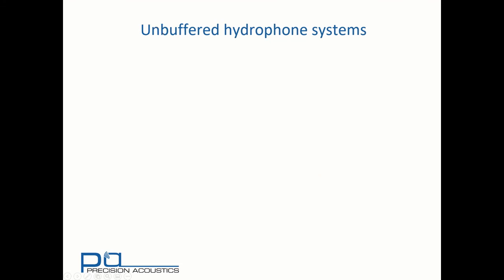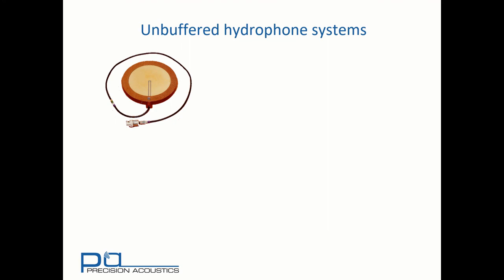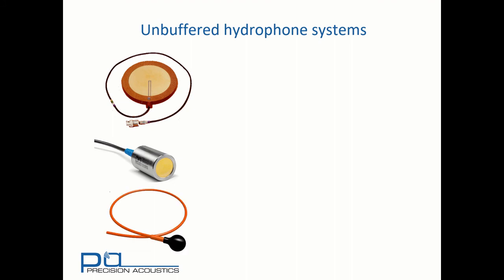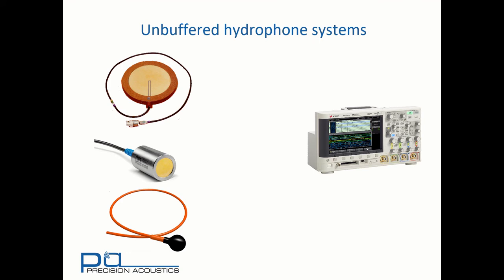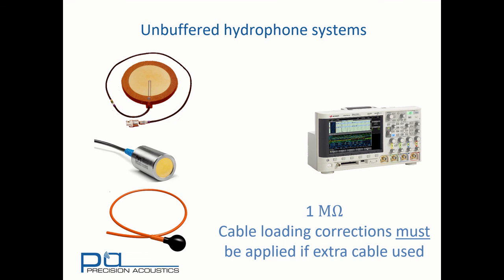If we have an unbuffered hydrophone system that doesn't incorporate a preamplifier — something like an older style Marconi membrane hydrophone, a piston hydrophone, or one of the ball or cylinder hydrophones that are common in underwater acoustics — these have their sensitivity determined at the end of cable, so must be connected directly to an oscilloscope using the one megaohm input impedance. If you put any additional length of cable between hydrophone and oscilloscope, cable loading corrections must be applied. In this case, it's recommended you contact the Precision Acoustics technical team for further information.